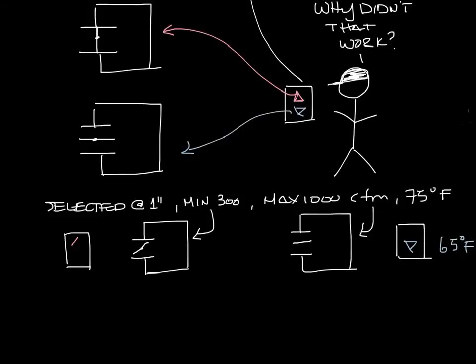And when he turns the thermostat to 85 degrees, the box controller sees that the space is 75 degrees, that's way too cold, and will drive the box to minimum CFM, not fully closed.